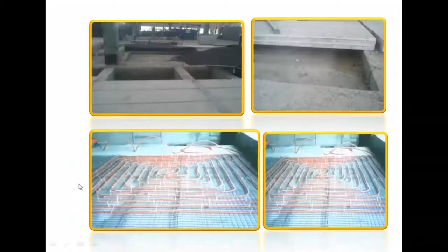Cold surfaces are created. Now this is another picture from another site where you can see the wire mesh and the pipes are tied to the wire mesh. This is known as a reticular method. Here the pipe goes inside and again comes back the way it has gone in. Alternate pipes are a supply pipe and a return pipe. So one pipe has gone inside and again it is coming out. This method gives you a uniform surface temperature.